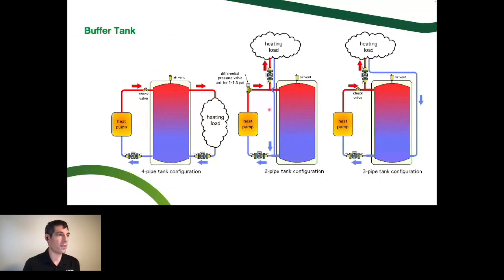That can be a really good fit if we've got a pretty wide range of flow rates and delta T's that are possible out into the system. So a 3-pipe configuration is similar. We're just always bringing the return back through the full thermal mass of the tank. So we're going to have to charge that all the way up each time. Depends on the system, and we've got a little bit more detail on that in Hydronics 17 as well.